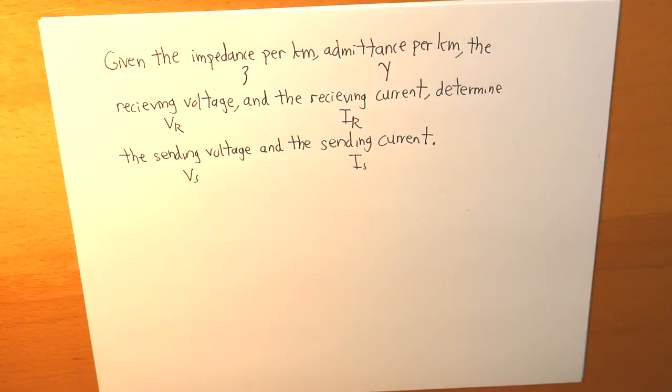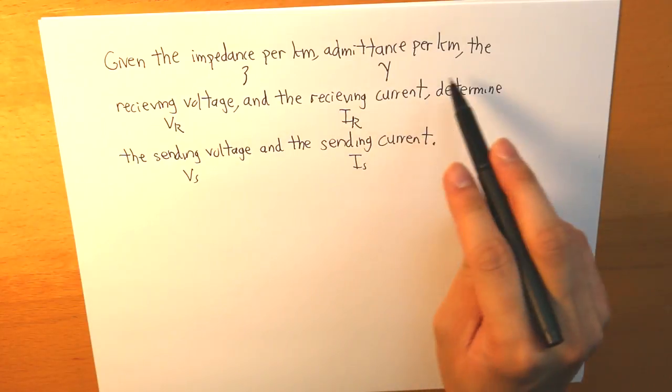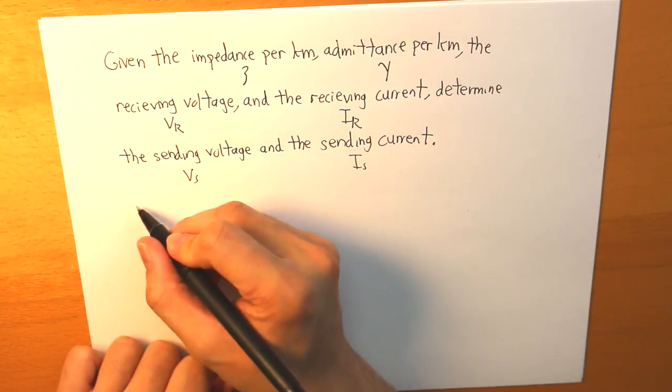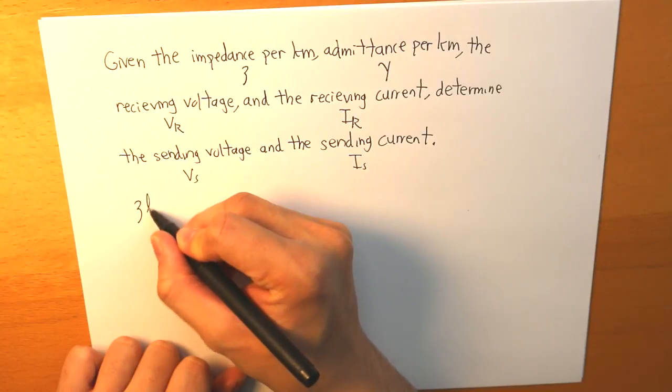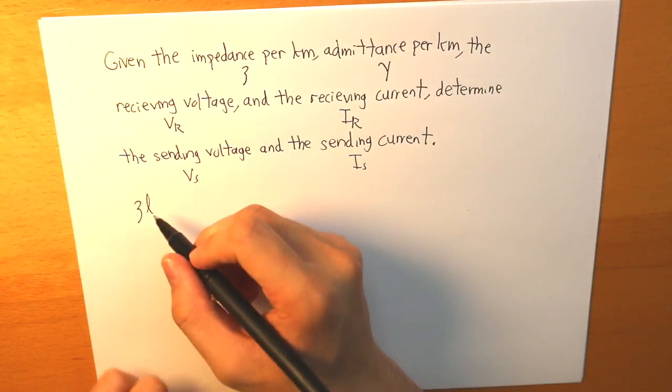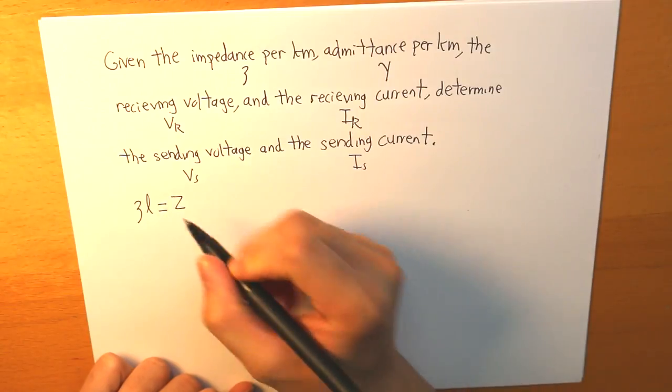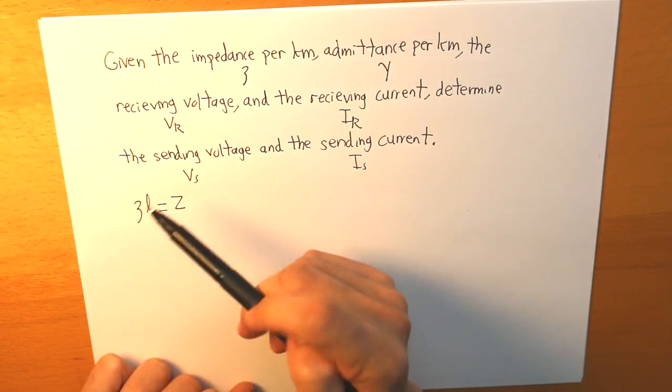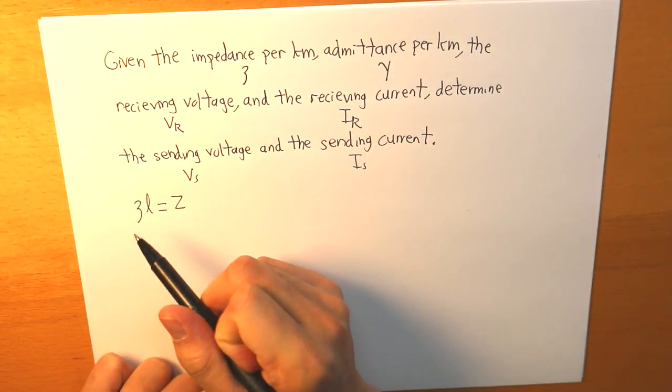Now, this is a pretty simple thing to do, involves matrices. So our impedance per kilometer and our admittance per kilometer, simply what we need to do is we just multiply each value by how long the transmission line is. And we will get our impedance and admittance for the total line.